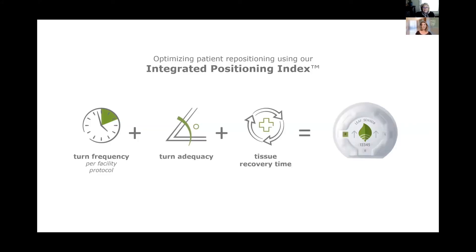The system is actually much more sophisticated than just a timer. We've been using timers forever — oven timers, paper clocks, musical cues — but this allows individualized care to be provided for each patient. It's not only looking at turn frequency, but also the adequacy of the turn, making sure the patient is repositioned enough to offload the sacral area, which is what we're trying to do to prevent pressure injuries. In addition, it looks at tissue recovery time between repositioning events — so if a patient has a very transient, short-duration turn on their side and returns supine, we're not going to grant them another two or three hours in that position before repositioning them again.